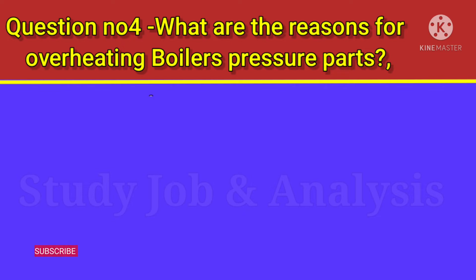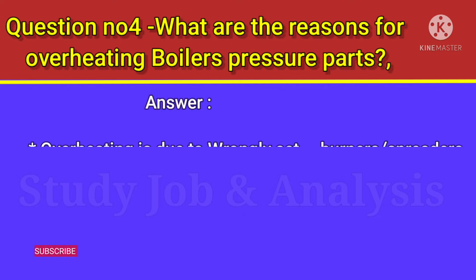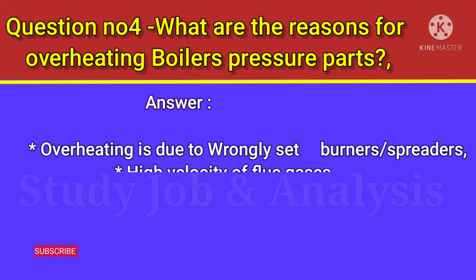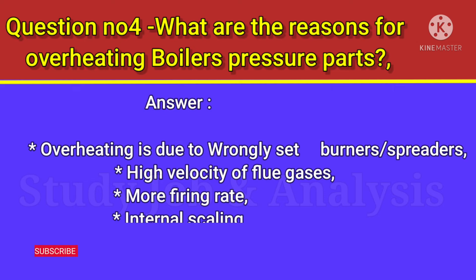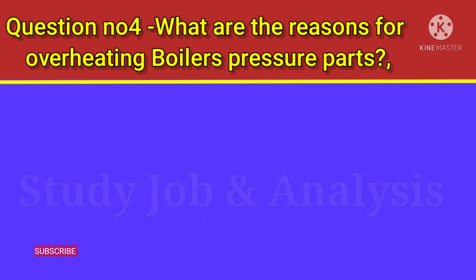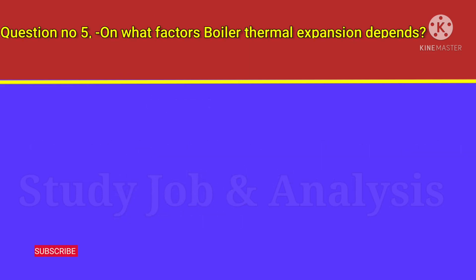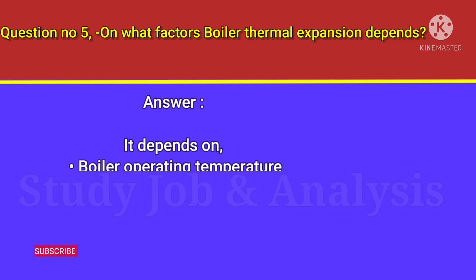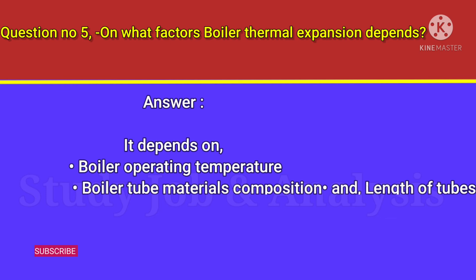Answer: Overheating is due to wrongly set burners or spreaders, high velocity of flue gases, high firing rate, and internal scaling. Question number five: on what factors does boiler thermal expansion depend? Answer: It depends on boiler operating temperature, boiler tube material composition, and length of tubes.